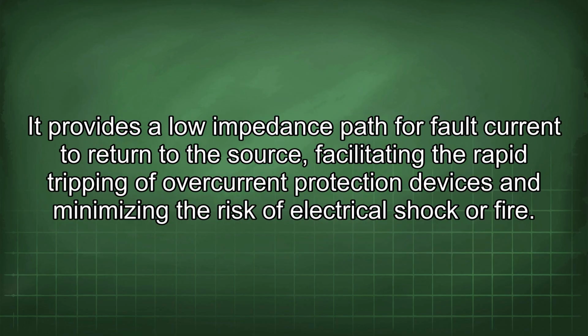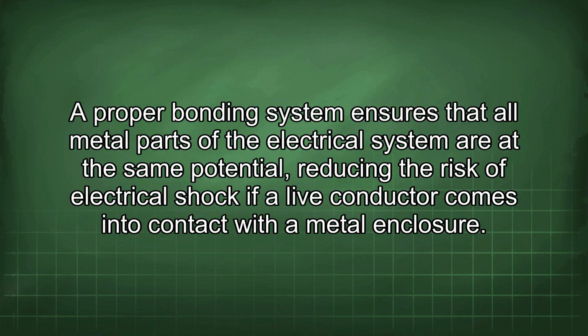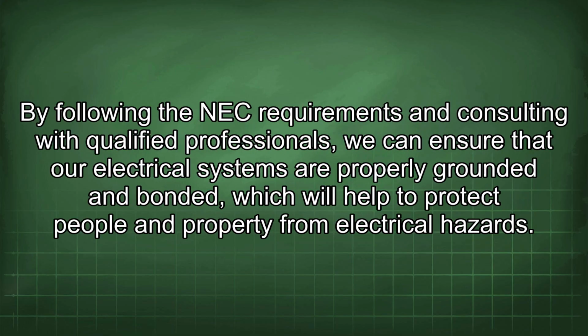It provides a low impedance path for fault current to return to the source, facilitating the rapid tripping of overcurrent protection devices and minimizing the risk of electrical shock or fire. A proper bonding system ensures that all metal parts of the electrical system are at the same potential, reducing the risk of electrical shock if a live conductor comes into contact with a metal enclosure. By following the NEC requirements and consulting with qualified professionals, we can ensure that our electrical systems are properly grounded and bonded, which will help to protect people and property from electrical hazards.